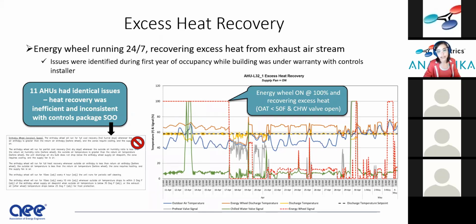This is a perfect example. Economizer is another one that I find a lot. Inefficient economizer control, it's not based on enthalpy, or it's not as intended in the control sequence. Again, things can drift over time. This control sequence is what, 40 years old, but in this case, I want to mention this was a new building. So this issue was found within the first year of operation. Why do we care about that? This was still under warranty, which is great because you can actually go to the controls installer and say, there's an issue with the sequence here. And in that way, I'm showing a way that analytics is used for continuous commissioning.